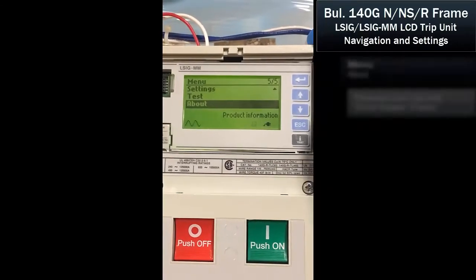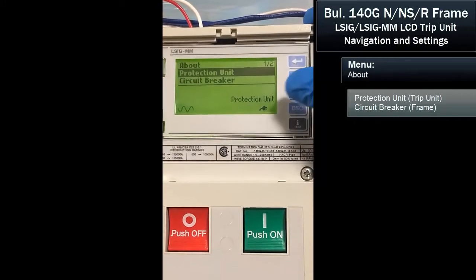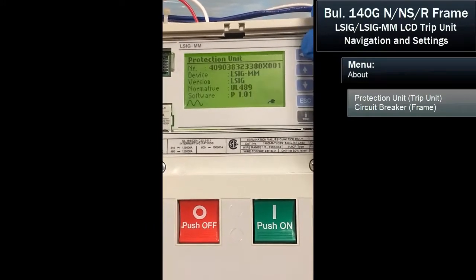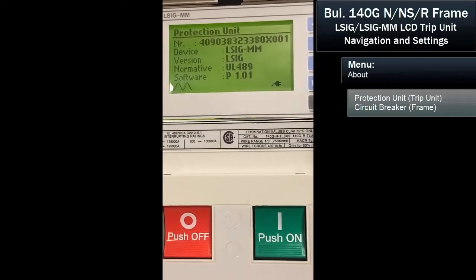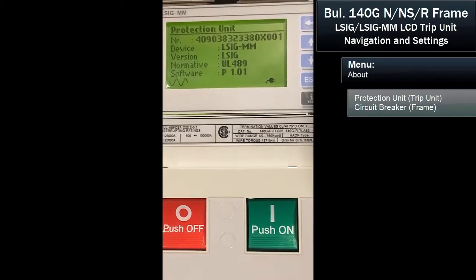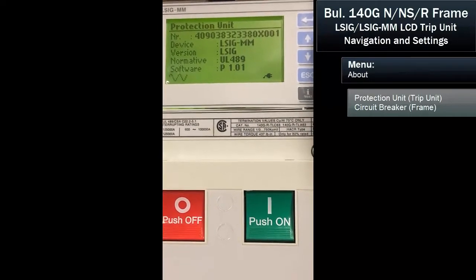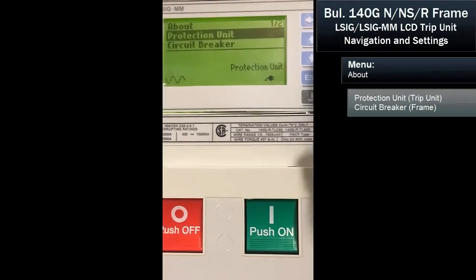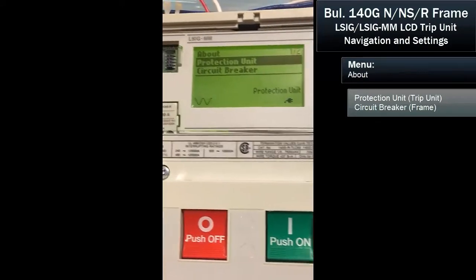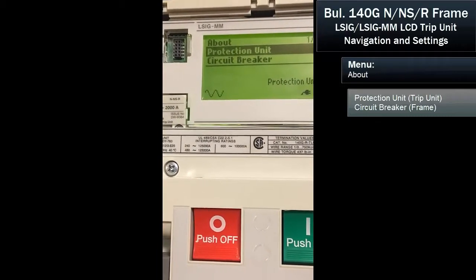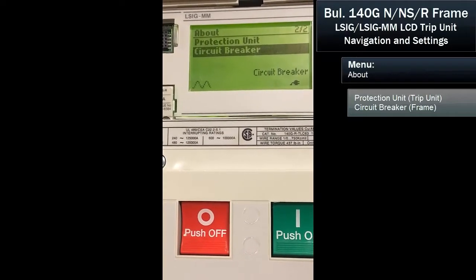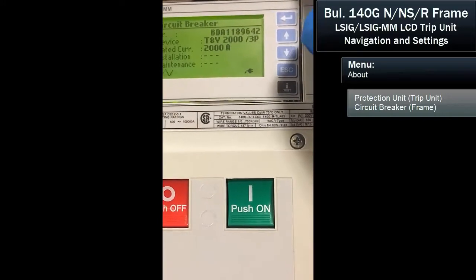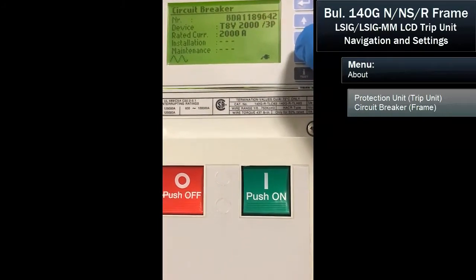The last item we can look at is the about menu. We hit enter for the protection unit — it'll give us the serial number, what type of trip unit it is, the protection type, which is UL489, and the software revision. We can back out and review more details about the circuit breaker, which shows us the 2000-amp serial number again, a three-pole device rated at 2000 amps.